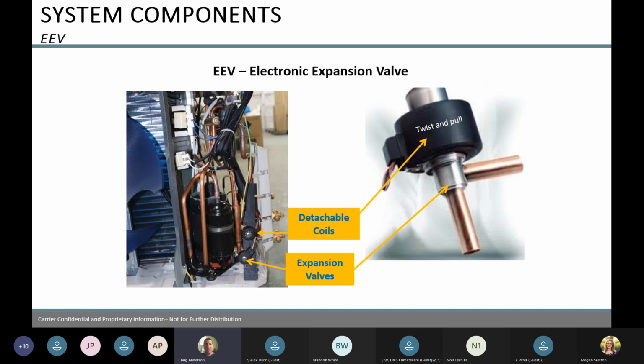EE valve. So this is monitoring the gas that's flowing through the unit. So our compressor is modulating. This valve is opening and closing to tell your sensor that's inside how much gas I'm going to put through this unit. Because we have a unit that's inside that can modulate from 3,000 BTUs to 9,000 BTUs. So this EE valve can move around 480 times. Whether it's opening or closing. So that's why we can't check pressures on these units, because we do not know what the compressor is doing or this EE valve. So always weigh it in. EE valve has a little twist on coil. It's got 6 wires going to it, and we'll go through that one next.